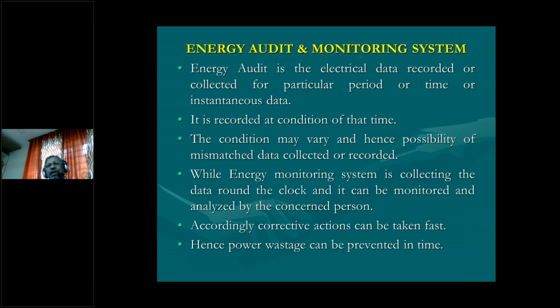Now, these energy meters are CT sensed meters, the standard 5 ampere meters. So you can provide CTs to your feeders. Now, where these meters can be provided, it depends. If there is any junk load, a bigger motor, you can provide it for those bigger size motors, for your pump motors, for your departments, or your process industry. And you integrate all those meters with your Cat6, Cat5 or any communication cable, according to that standards, or simply this shielded twin core cable also works for some applications.